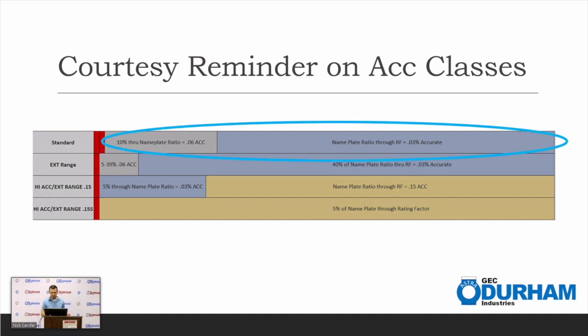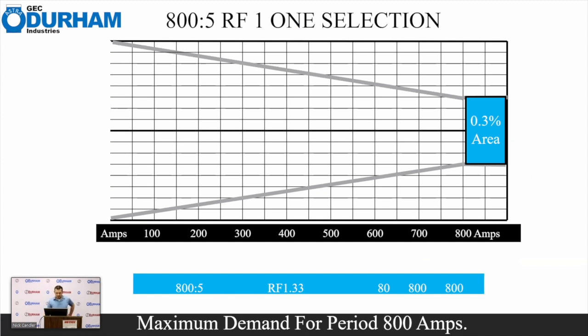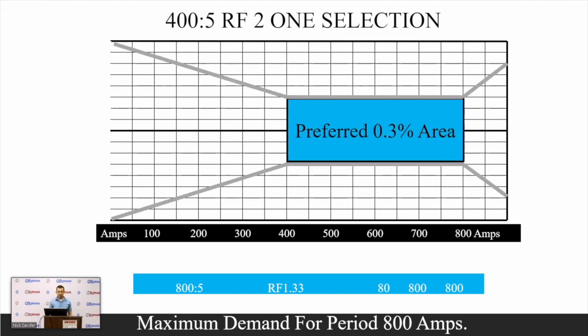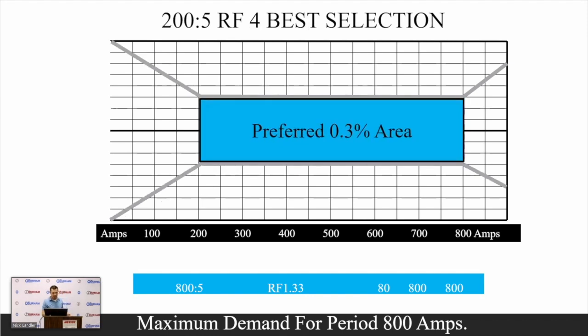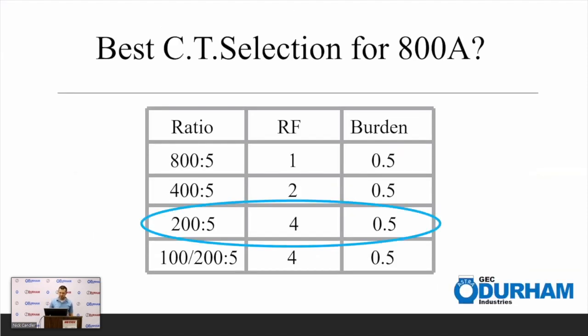Okay, so we're going to look at a 0.3 accuracy transformer, and again, at 100% of the nameplate value is where that 0.3 accuracy kicks in. So if we have demand for 800 amps and we put that 800 to 5 transformer into service, it doesn't have much margin in that 0.3 accuracy. You'd actually be running in the lesser accuracy class for the bulk of the use, probably. Now we could put a 400 to 5 ratio in there. It's got a rating factor of 2, so that gets you from 400 amps to 800 amps. That's pretty decent. But if we size by the rating factor and we pick a 200 to 5, we have a much greater range to generate revenue in that ideal accuracy range. So the best selection for this is going to be your 200 to 5, rating factor of 4, 0.5 burden.